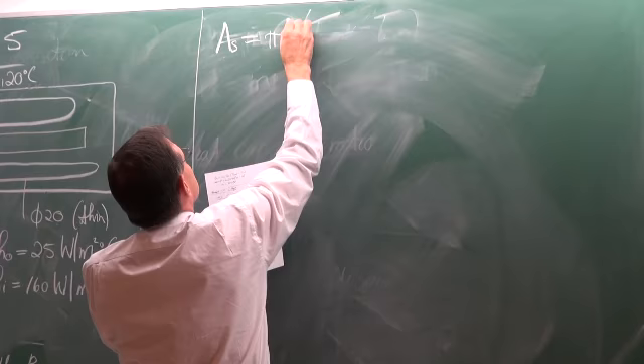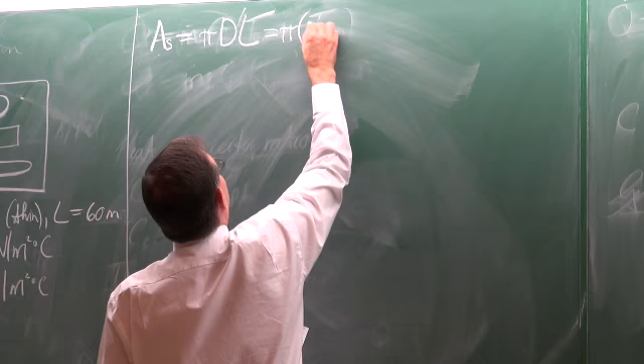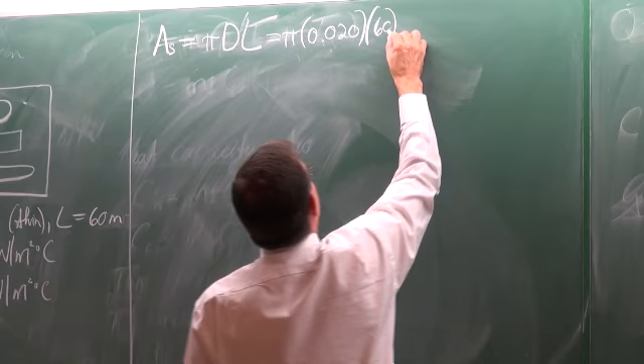We are going to need the surface area of the tubes. It is pi times diameter times length, so A equals pi times 0.020 m times 60 m, which gives a surface area of 3.77 square meters.